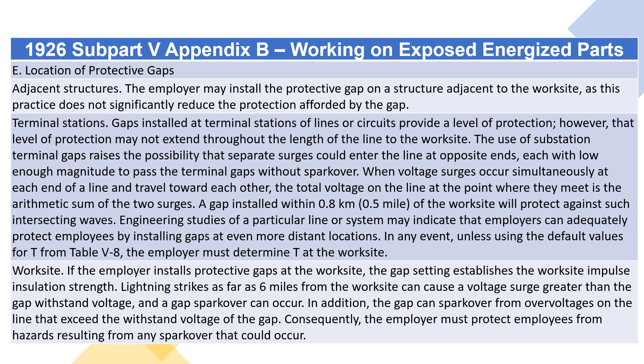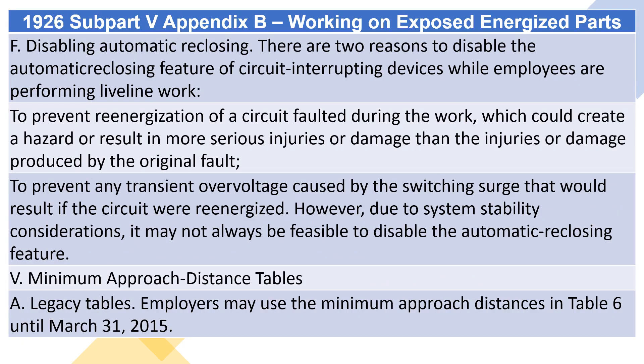Disabling automatic reclosing: there are two reasons to disable the automatic reclosing feature of circuit-interrupting devices while employees are performing live-line work. First, to prevent re-energization of a circuit faulted during the work, which could create a hazard or result in more serious injuries or damage than the original fault. Second, to prevent any transient overvoltage caused by the switching surge that would result if the circuit were re-energized. However, due to system stability considerations, it may not always be feasible to disable the automatic reclosing feature.